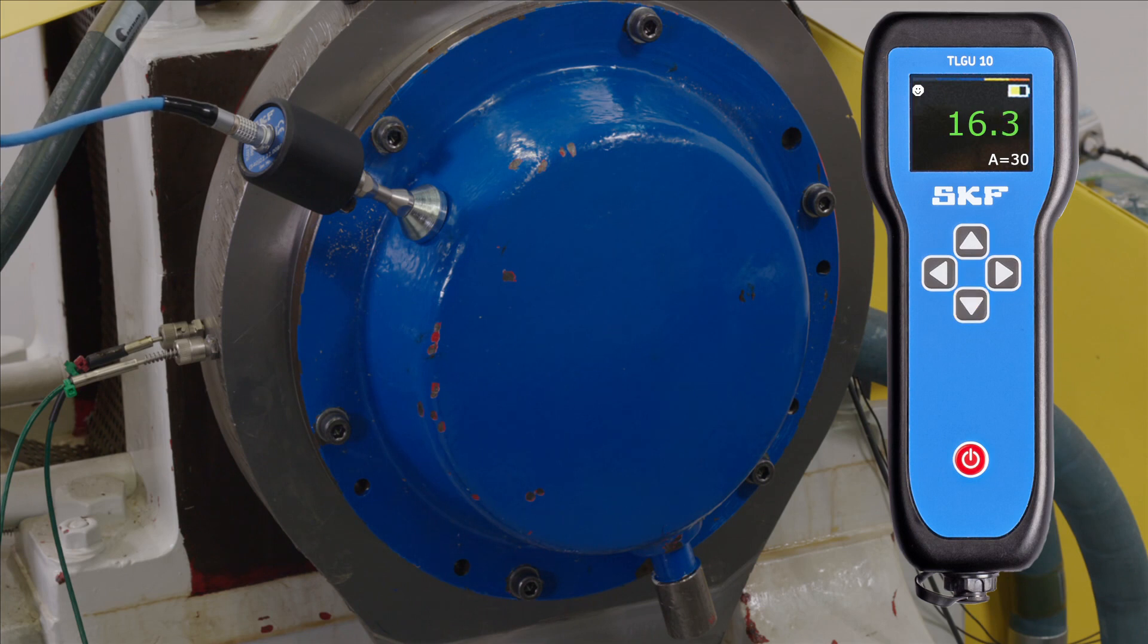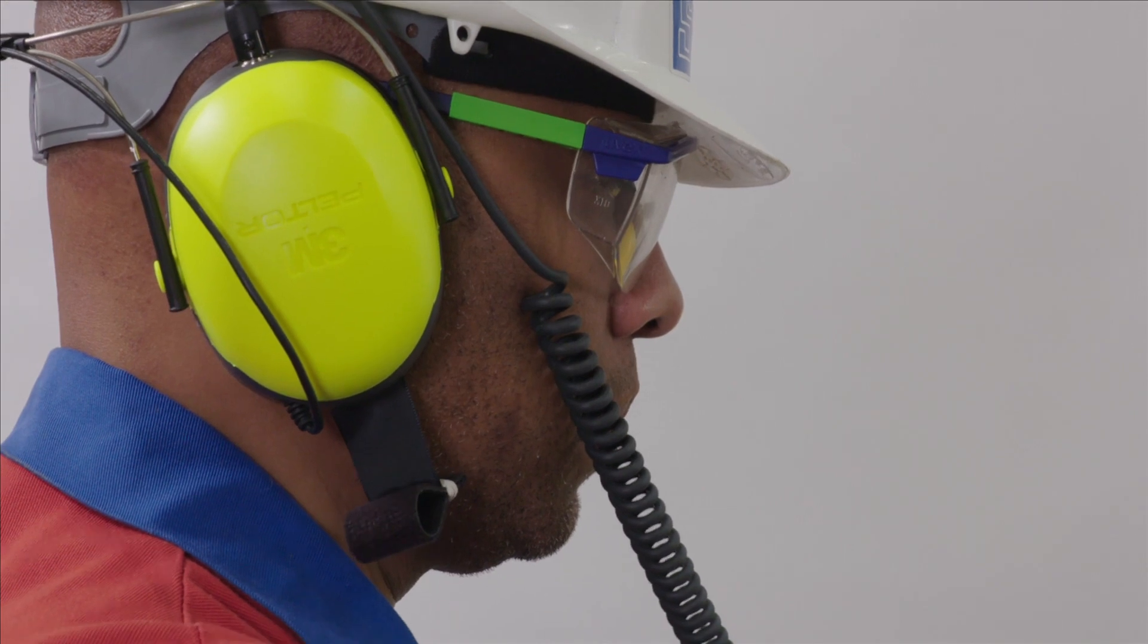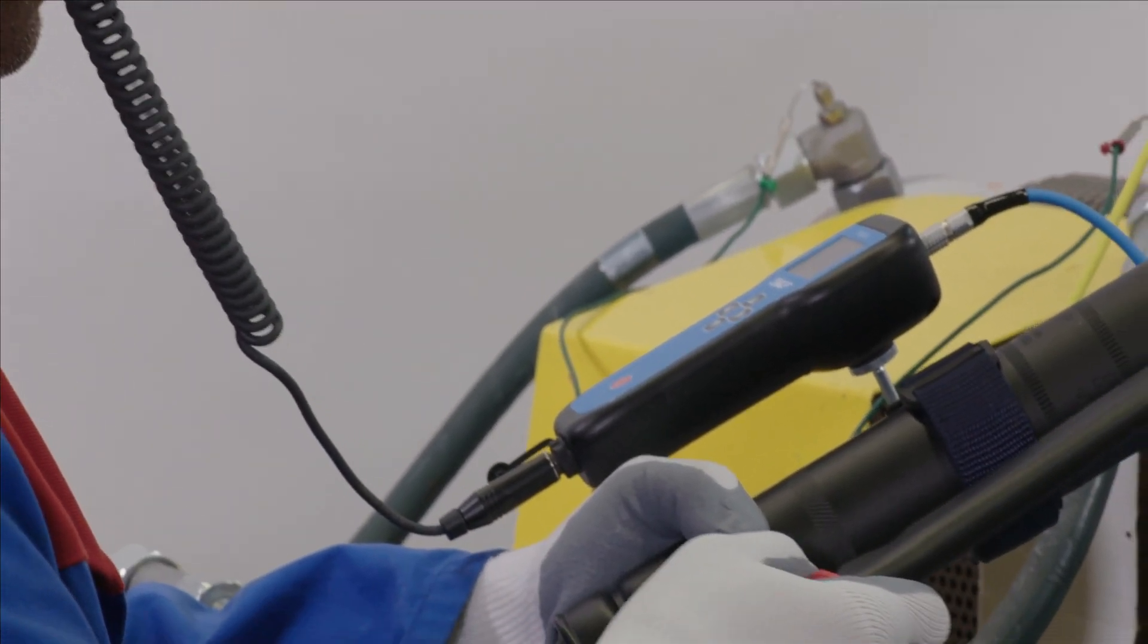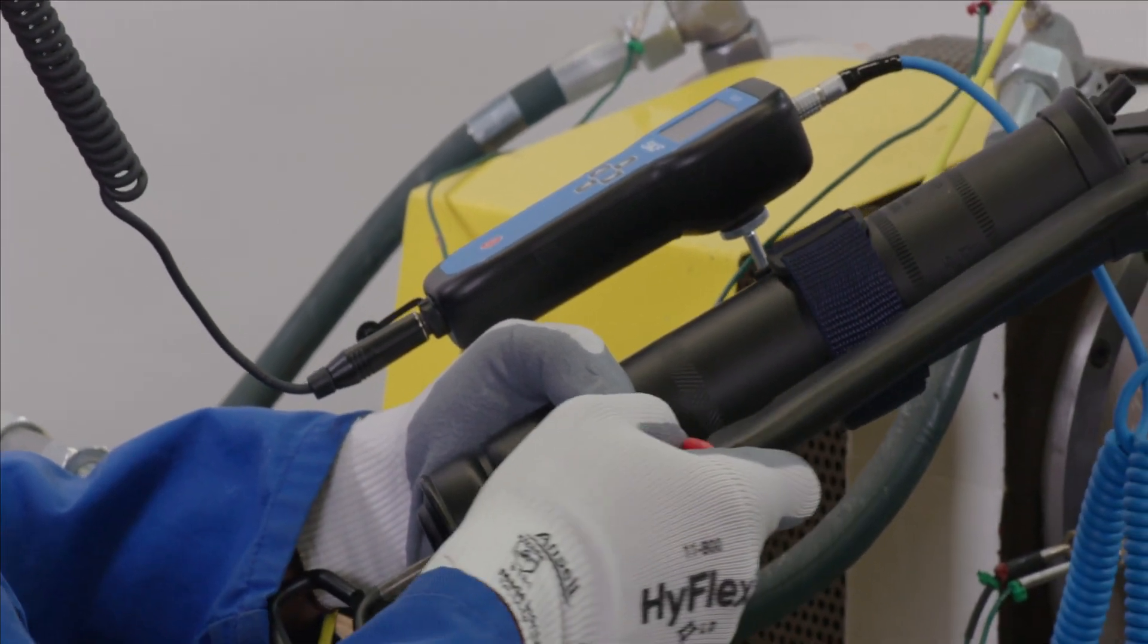The noise level reduces as the first indication that the lubricant is effectively reaching the bearing, which is valuable information when using remote lubrication.